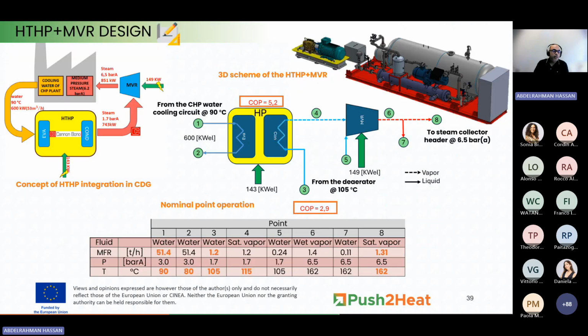So based on this, we put together this concept of integrating a high temperature heat pump in CDG, as you can see in this concept diagram. We will recover heat from 90 degrees water. We will recover approximately 600 kilowatts at the high temperature heat pump, which will consume 143 kilowatts of electricity. It will produce saturated steam at 1.7 bar A. Next, we will use mechanical vapor compression technology to increase the pressure to 6.5 bar A.